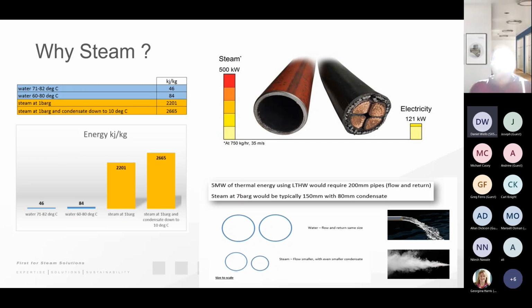Now, quite often when we're talking to the industrial, the manufacturing sector, from time to time an energy manager or a sustainability manager may mention to us the viability of a heat pump as an alternative. Now, just to make things clear, there's absolutely nothing wrong with a heat pump. We've got absolutely no argument with a heat pump, and heat pumps very much have a place in certain processes. But for processes that require a significant temperature or a significant heat content in the primary media, heat pumps are likely to be completely unable to achieve that pressure-temperature relationship that steam can.